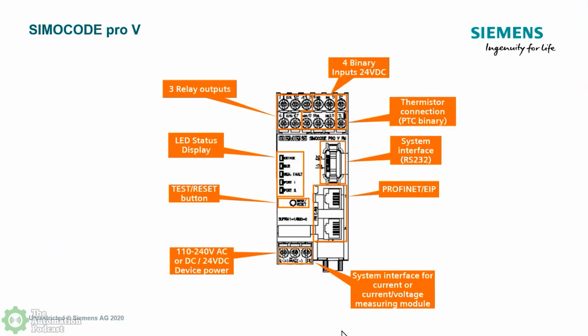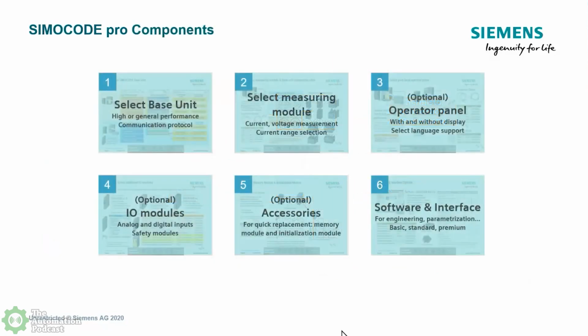So, and then up underneath is where the current transducer or voltage transducer plugs in. And then you can see that there's 2 excitation voltages for it, 110 to 240 volt or 24 volts DC. So quickly, so we can get into the heart of things, the number 2 things you need to do is select the base, what voltage, what communication protocol you want, and then what amperage you're going to use for it. And then everything else is optional.